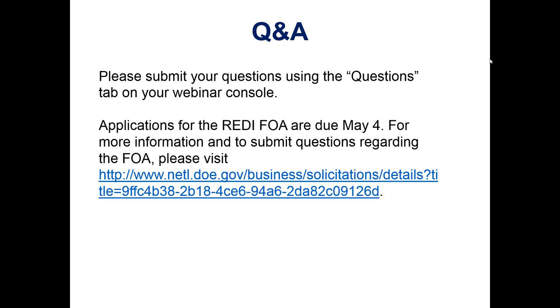Regarding stored hydrogen from water hydrolysis, is that regarded as a viable approach? Well, some people consider it viable. In particular, there's a lot of interest in it in Europe. The trouble is, unlike other storage technologies, it has a much further way to go. The thing is that you lose a lot of energy when you hydrolyze water. You then have to store it, and then you have to use it in the fuel cell. Or alternatively, you can put hydrogen directly into the gas pipelines. But the system is as yet much too expensive, and the energy goes against you, so you really have to have basically free energy.